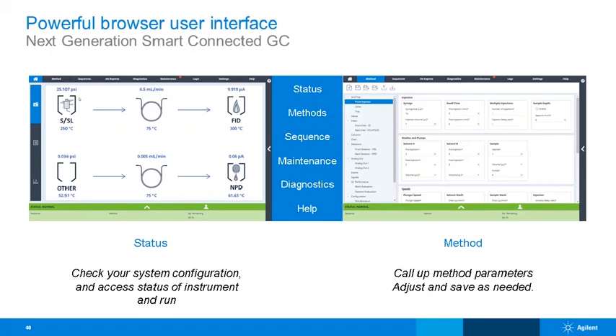So let's look into the browser interface for all of these GCs in a little bit more detail. So here we have on the left-hand side an example of status, and this is basically a dual channel system, quite clearly, with an FID and an NPD, and you can see the temperatures and the flow rates that are currently happening on the instrumentation. And then if you go on the right-hand side, you can actually put methods straight into the GC should you require it, or this would be obviously if you don't have a data system next to the instrument or a LIMS system, etc. But still.